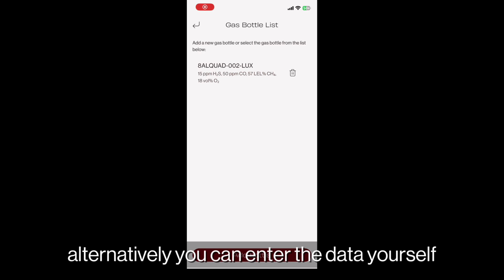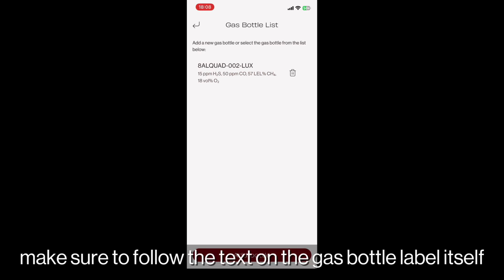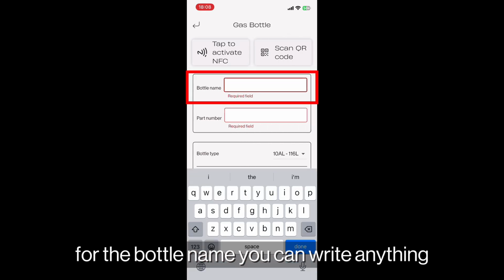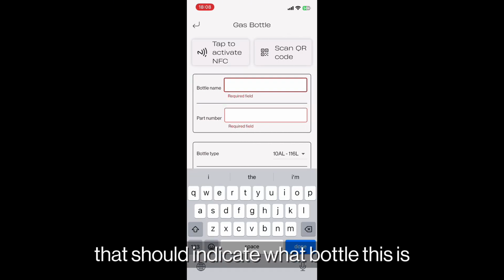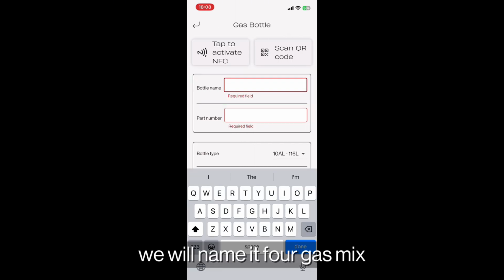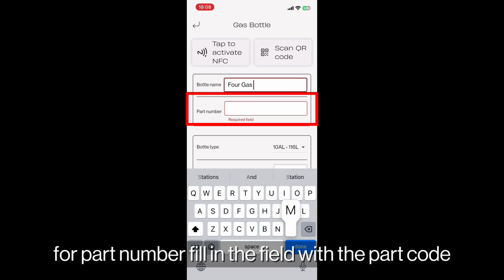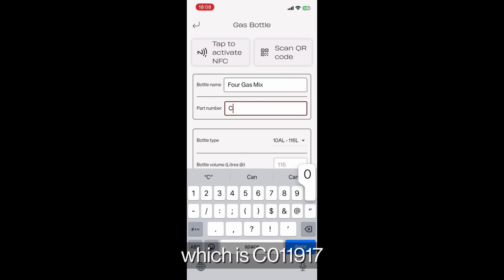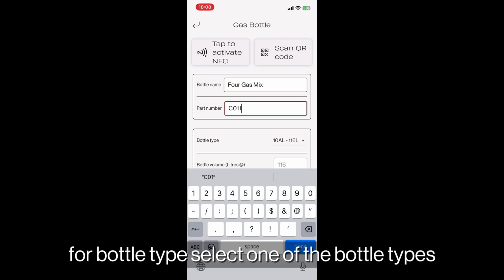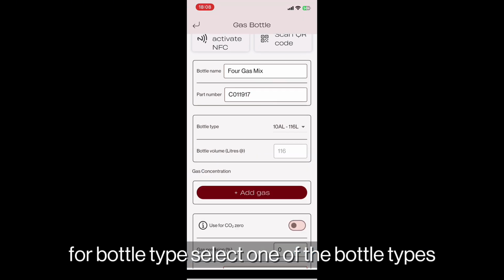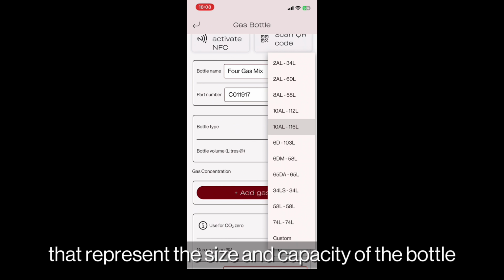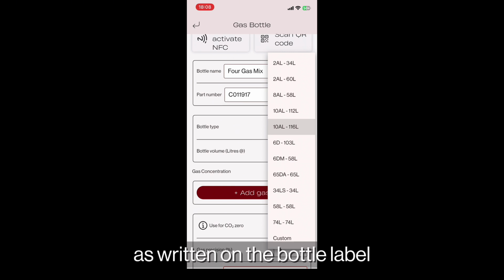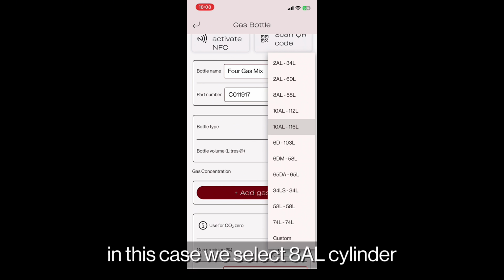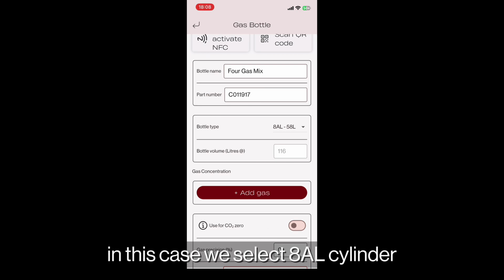Alternatively, you can enter the data yourself. Make sure to follow the text on the gas bottle label itself. For the bottle name, you can write anything that should indicate what bottle this is. We will name it 4-gas mix. For part number, fill in the field with the part code, which is C011917. For bottle type, select one of the bottle types that represent the size and capacity of the bottle as written on the bottle label. In this case, we select 8 AL cylinder.